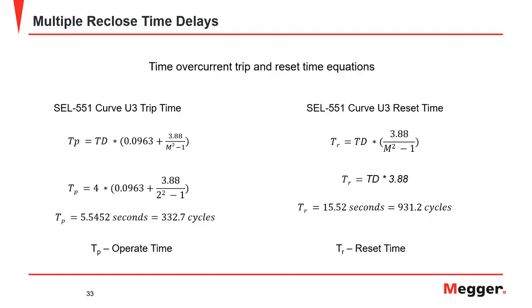If you see there, Mike is using multiple 2, which means that whatever the pickup was, we are injecting twice as much current to that relay or to the fault, and we're getting that time. That's the way we make the curve independent of the actual amount of current, and we make it dependent only on the pickup value that we choose.